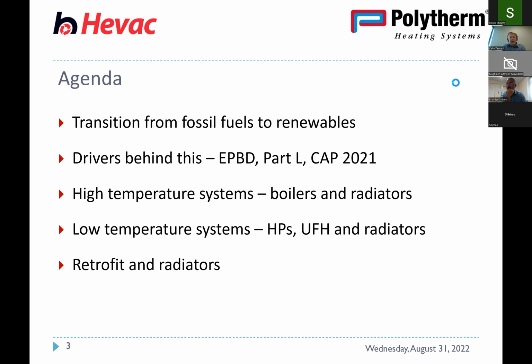And then we'll look a bit at retrofit and at radiators. As I said, the suitability of putting in a heat pump in a retrofit scenario. Can we use the existing radiators or the existing cylinder, or do we have to resize them? And the new trend of emitters, looking a bit at the cooling end of things.